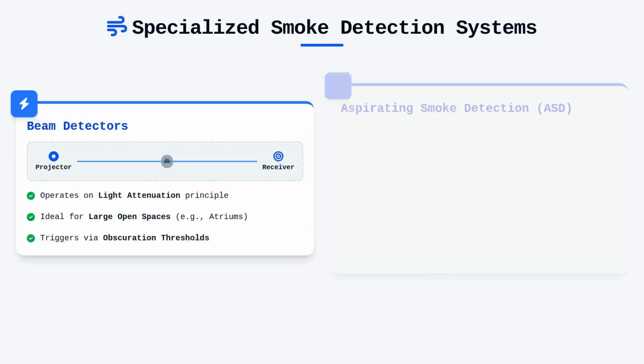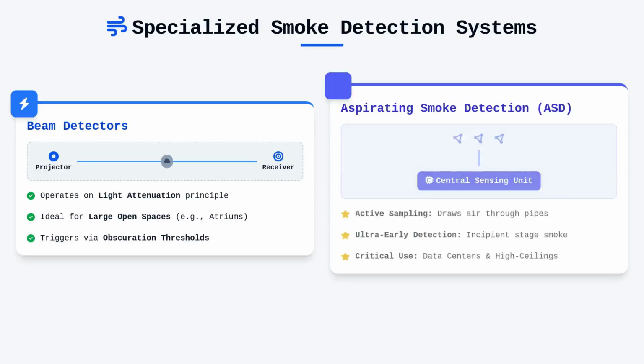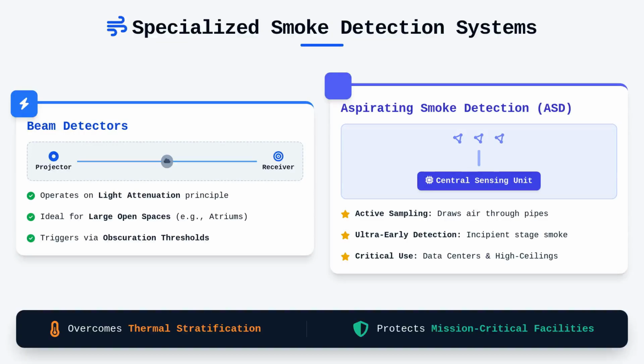percentage. Aspirating smoke detection, or ASD, takes this a step further by actively drawing air samples through a network of pipes to a centralized sensing unit. This allows the system to detect incredibly low concentrations of smoke, making it indispensable for mission-critical facilities like data centers, where early, incipient stage detection is vital. Because these systems sample air directly, they are largely unaffected by thermal stratification, which often prevents smoke from reaching ceiling-mounted sensors in high-ceiling environments.